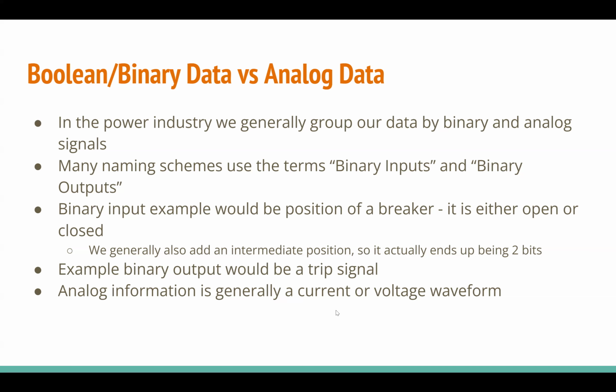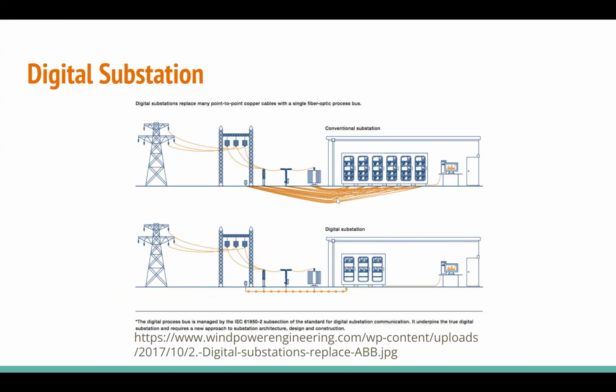So if we have too much current, we open a breaker and stop electricity from flowing. These types of things were actually what we did not digitize in the past. The binary inputs and outputs, and the analog waveforms, are the stuff actually being sent on these pieces of copper out into the yard. Here would be our circuit breaker, current transformer, or voltage transformer, all with these old hardwired connections.